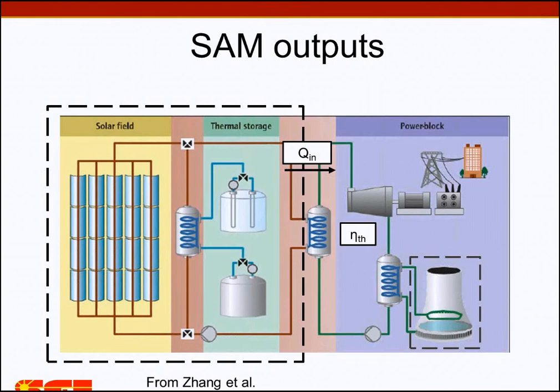I can also get an hourly thermal efficiency value, shown on the right-hand side. The left-hand side is what I wanted System Advisor Model to handle — choosing and sizing the solar field. So I output that heat input to the power block, and then instead of modeling the power block myself, I grabbed that thermal efficiency and assumed I'm not changing anything about how the power block operates — importantly, not changing the condensing temperature at this point. This allows me to estimate the heat rejection required to run that power plant.